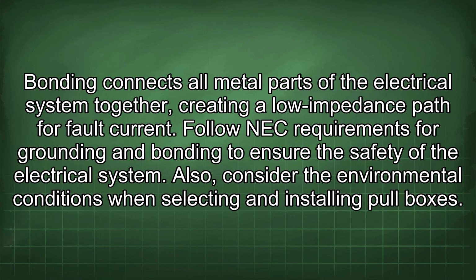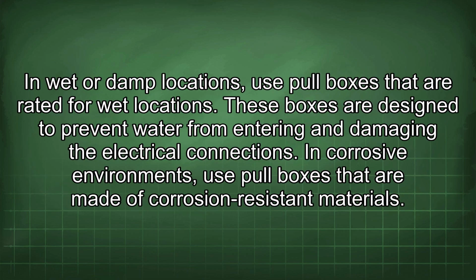Also, consider the environmental conditions when selecting and installing pull boxes. In wet or damp locations, use pull boxes that are rated for wet locations. These boxes are designed to prevent water from entering and damaging the electrical connections. In corrosive environments, use pull boxes that are made of corrosion-resistant materials.